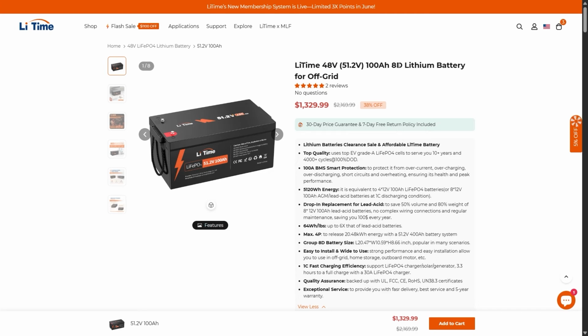This is a 100 amp hour 8D lithium iron phosphate battery, not a lithium ion battery. Lithium iron phosphate can last 4,000 plus cycles up to 100% depth of discharge, meaning you can discharge it 100% over 4,000 times before noticing any capacity differences.